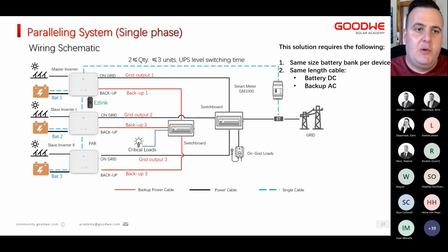Now let's have a deeper look at the paralleling system. There are 2 ways to do the parallel. This is the first way, which is currently 100% approved from our R&D side. So 2 to 3 units paralleling will give you UPS level switching time. As I mentioned, the EasyLink will be in your master inverter and no Wi-Fi modules in any of the other inverters. These connect via RS485 to one another. The EasyLink does come with 2 cables to connect 2 inverters or 3 inverters to each other.